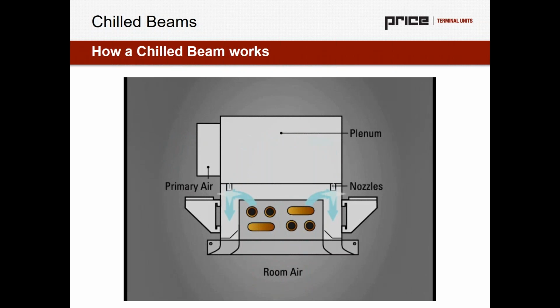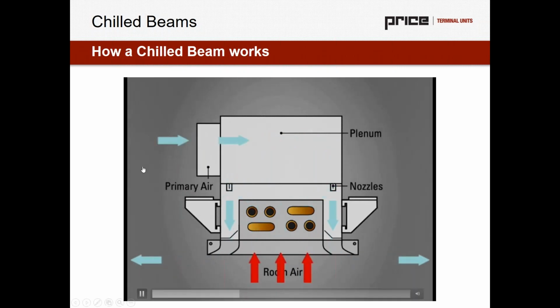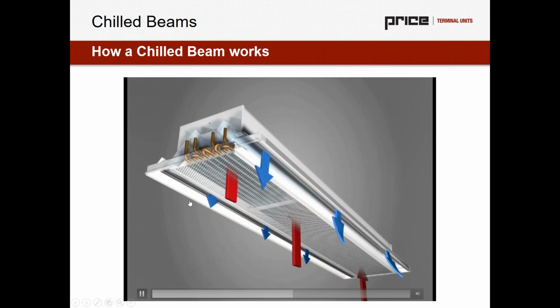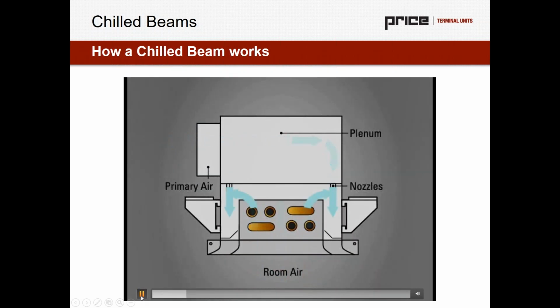So when we look at how a chilled beam works, I just want to show this on screen here to review. We have that primary air being supplied into the chilled beam, and that primary air is accelerated through these high velocity nozzles. We can see that on screen here. I'm going to click pause. That airflow goes into this back plenum, is supplied at a high velocity through the nozzles and thrown to the space. And because of that high velocity air, we're entraining and inducing additional airflow through the face of the coil, which we can cool or heat to our requirements, and it's being supplied once again to the space.